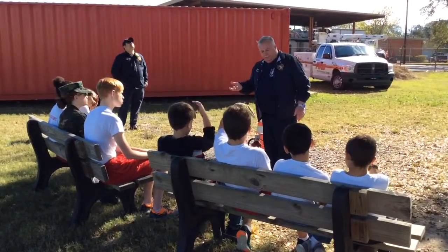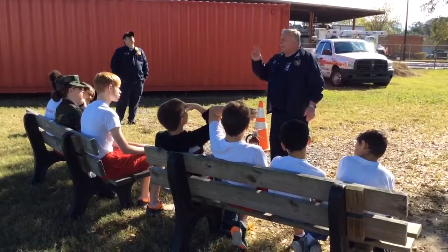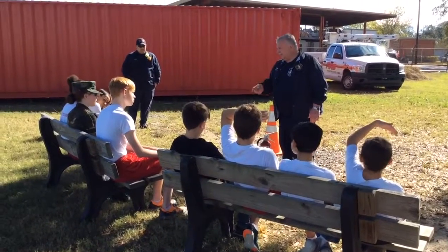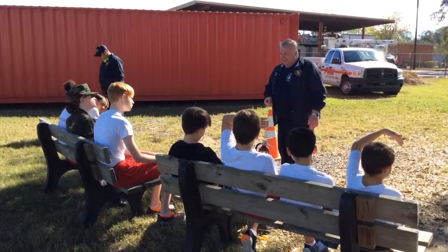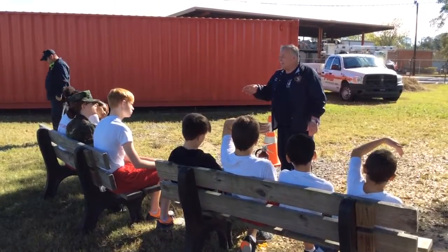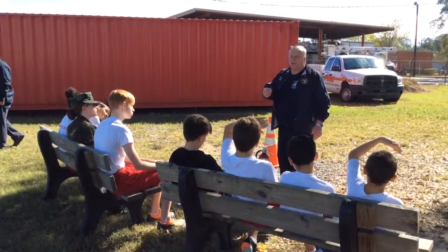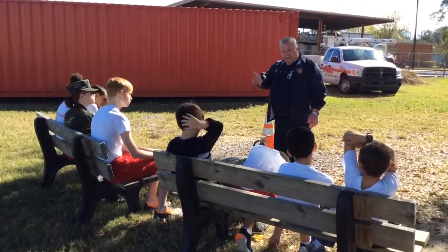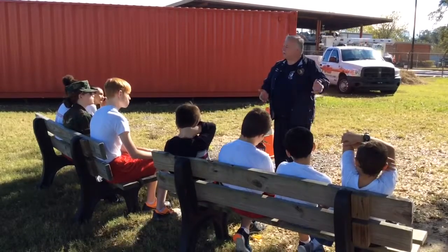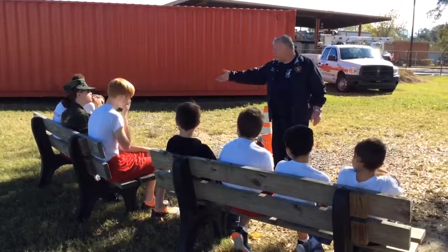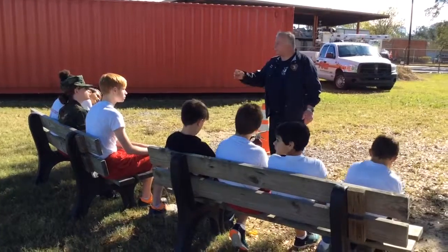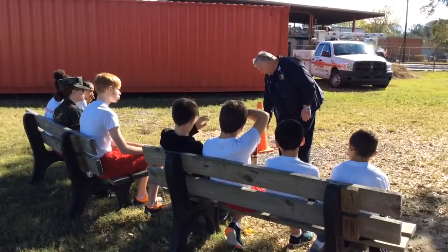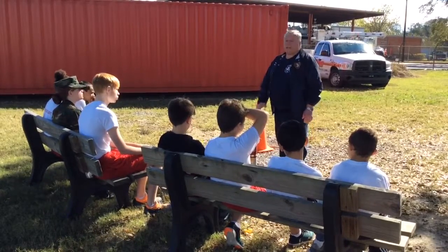So what would y'all say a CO2 extinguisher's class is? B and C. So a CO2 is good for B, which is boiling liquids, flammable liquids, gasoline, diesel fuel, or C, which is electrical. Okay, so a CO2 extinguisher is a BC fire extinguisher. All right, so we're going to just worry about this one today. It's ABC. It's good for anything.